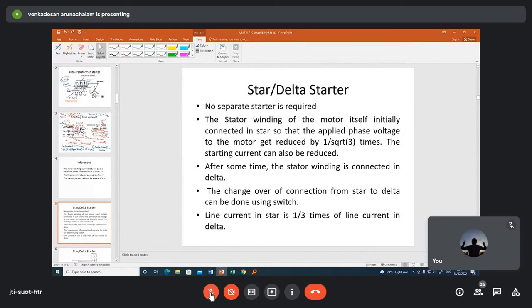The stator winding of the motor itself, during starting, is connected in star, so that the applied phase voltage to the machine gets reduced by 1 by √3 times. The starting current can also be reduced. After some time, during running time, the stator winding is connected in delta. The changeover of connection from star to delta can be done using a switch. So the line current in star is 1 by 3 times the line current in delta. Because of this reduction in voltage, the current also is getting reduced.